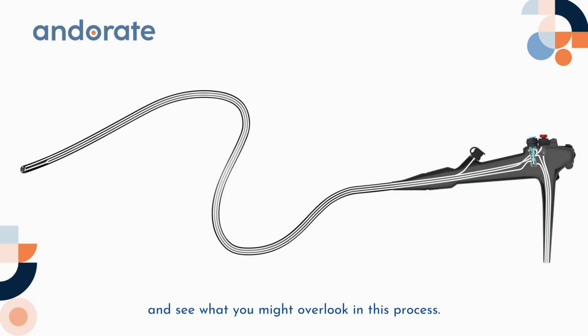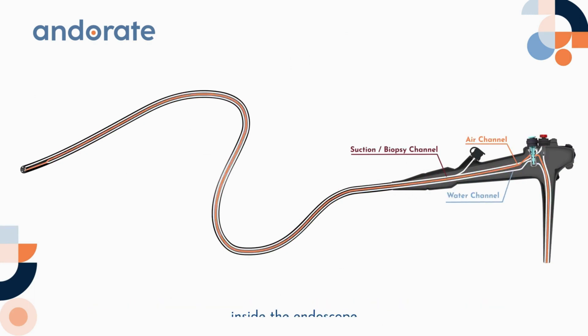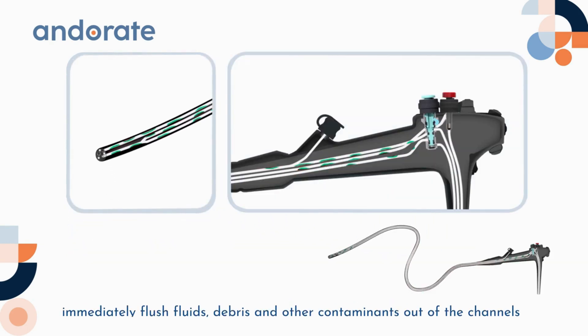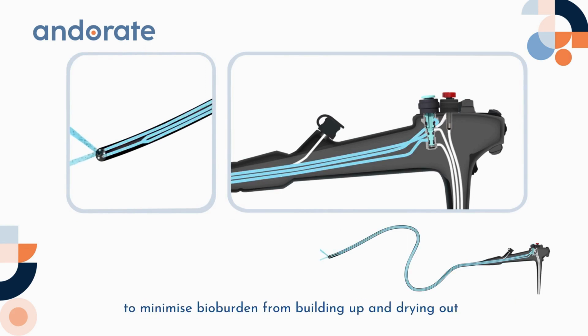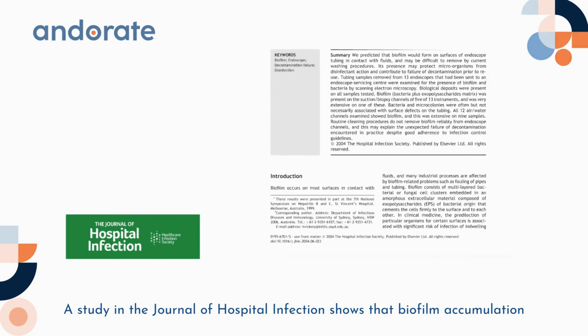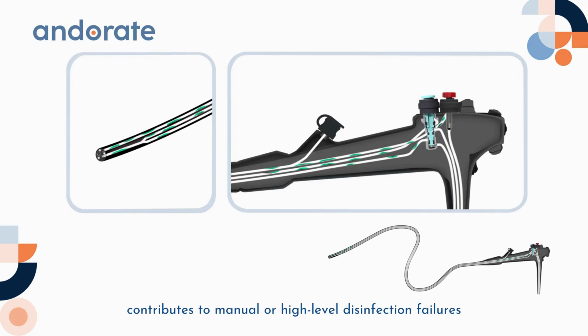It is commonly known that the suction, biopsy, and air/water channels inside the endoscope can get heavily contaminated during endoscopy. Therefore, after the procedure we should immediately flush fluids, debris, and other contaminants out of the channels to minimize bio-burdens from building up and drying out. A study in the Journal of Hospital Infection shows that biofilm accumulation contributes to manual or high-level disinfection failures, which can lead to cross-contamination with infectious diseases.